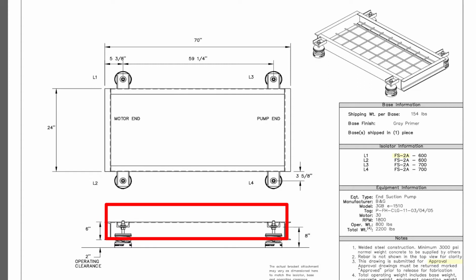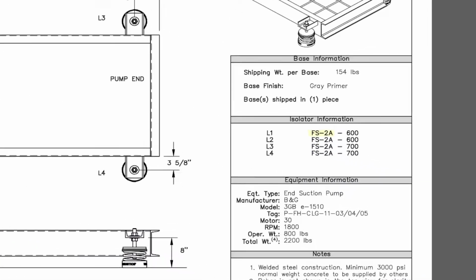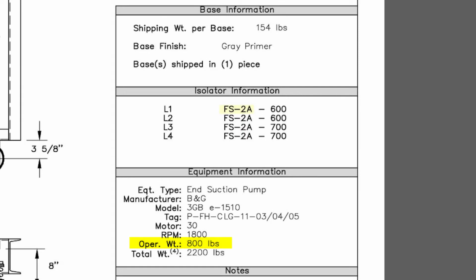In cases where weight must be kept to a minimum, the base can be kept thinner and more support points added. While it is possible to make inertia bases as thin as 4 inches, it is most common and recommended industry practice to not go any thinner than 6 inches. It is also industry standard practice for the inertia base to weigh at least what the equipment weighs.